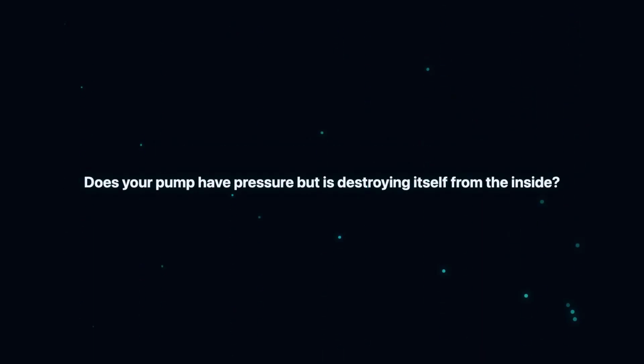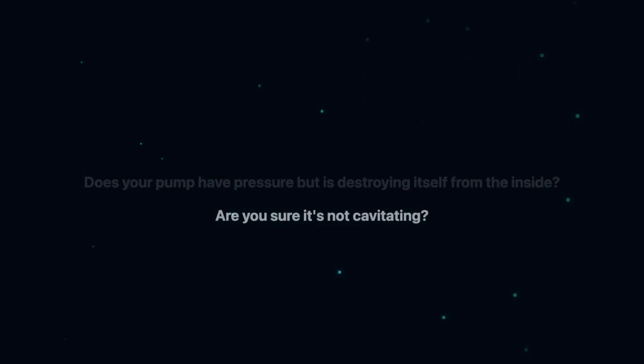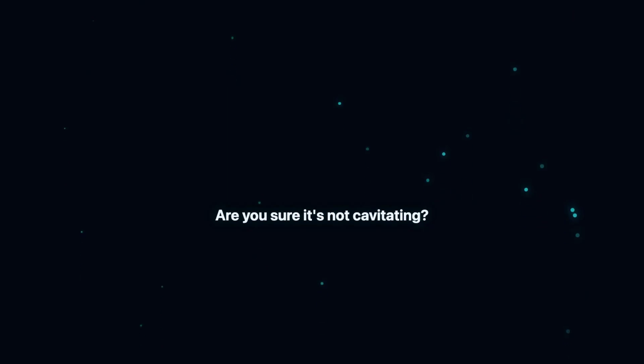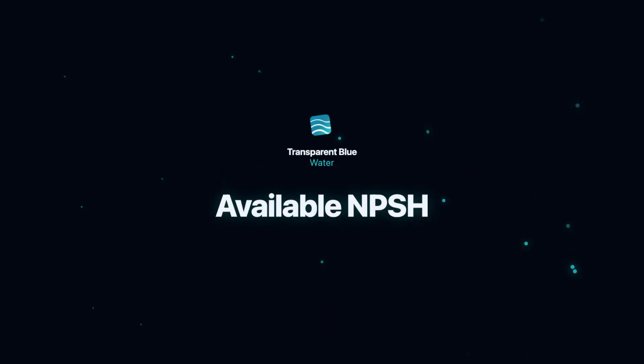Does your pump sound like it's pumping gravel or rocks? Do you know why your pump has pressure but is still being destroyed from the inside? Are you sure your pump is not cavitating? This is called cavitation, and the culprit is usually a bad NPSH calculation. Today we calculate the available NPSH for a suction system.